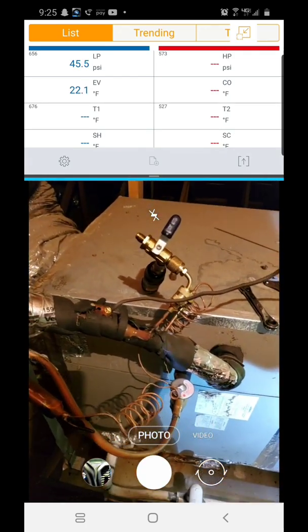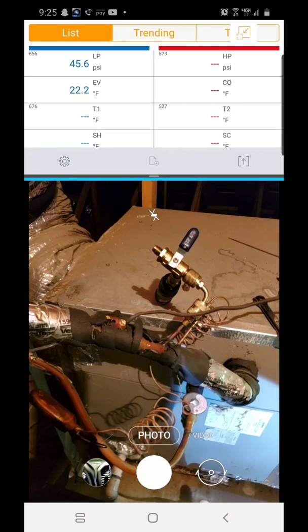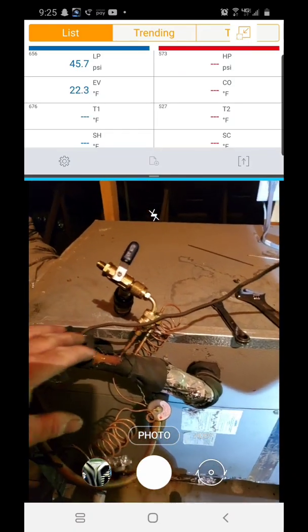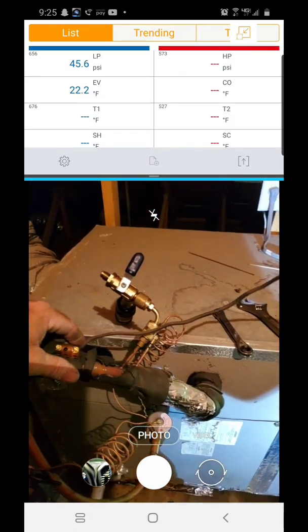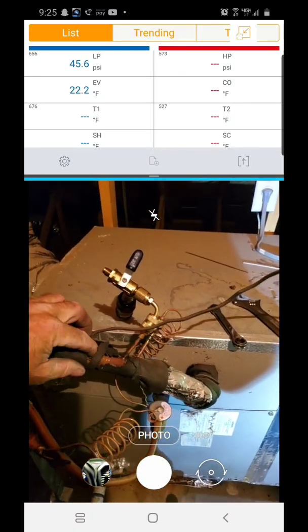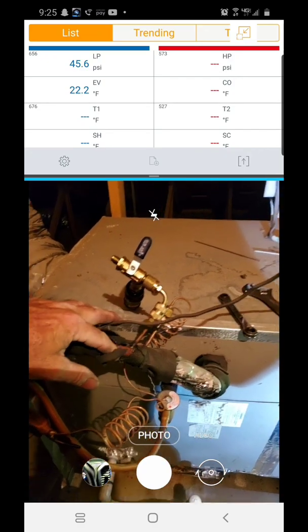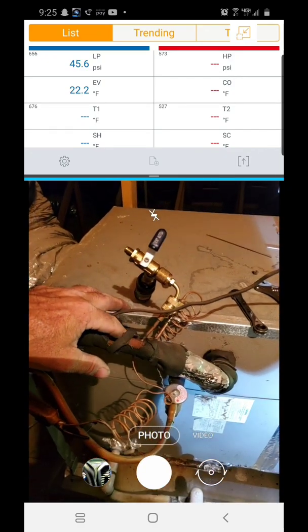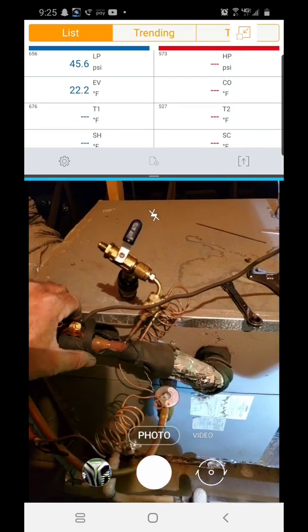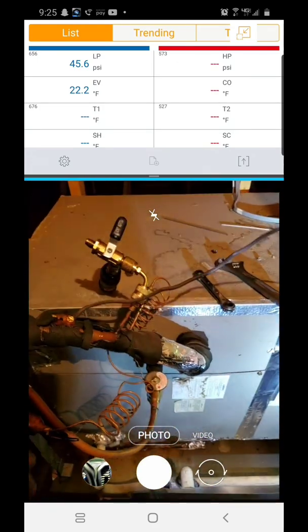But I noticed there was some bearing play in the motor. The outdoor fan motor probably just went out but then reset before the compressor did. So I changed that motor - it was worn, had bearing play. But then we noticed since I did that earlier today that it hasn't cooled.